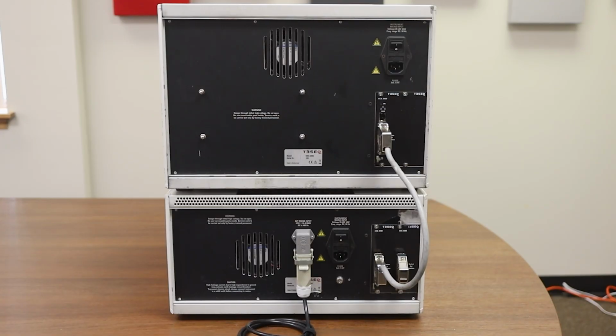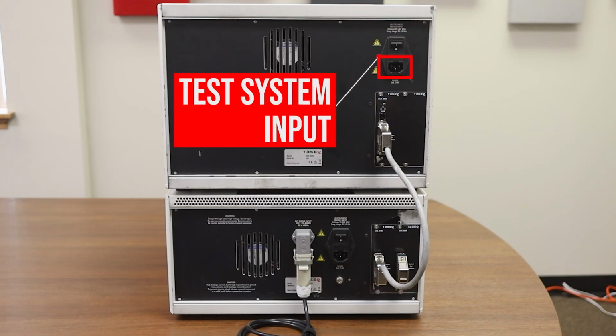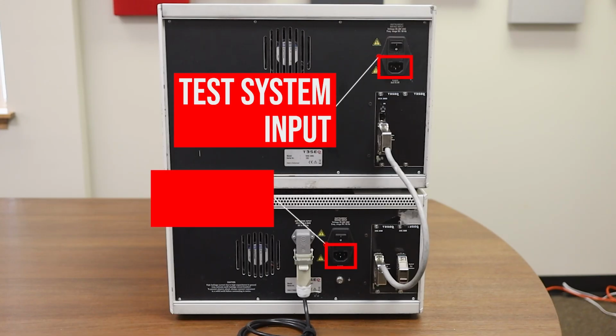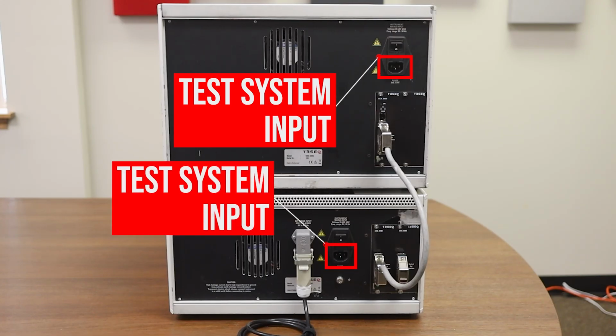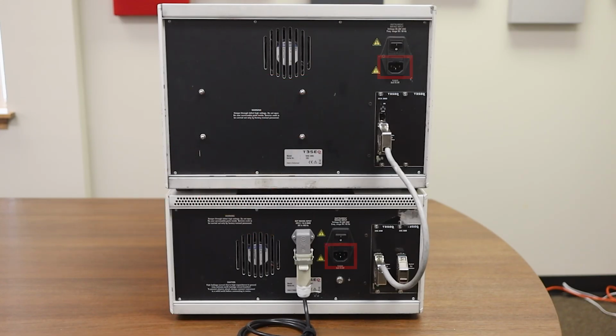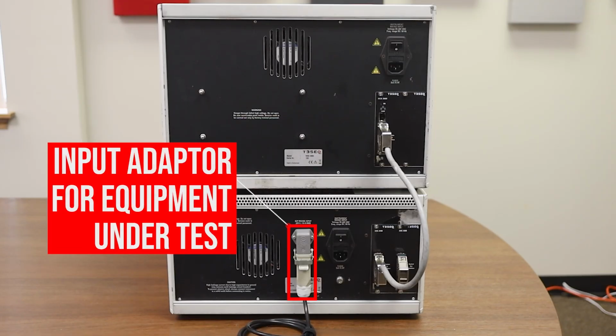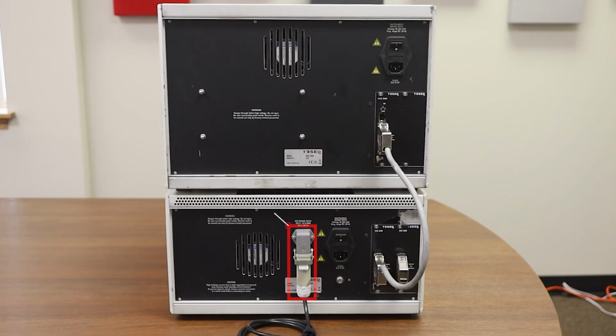There are also some less serious connection mistakes, and we see this often with the Teseq NSG 3060 in front of us now. There are two plugs for the inputs for the test system, and one's going to be on top with the NSG 3060, and the bottom is going to be with our CDN 3061. And then we also have a gray input adapter for our equipment under test. It's important to be sure that both the system power inputs are connected in order for the system to be operational.